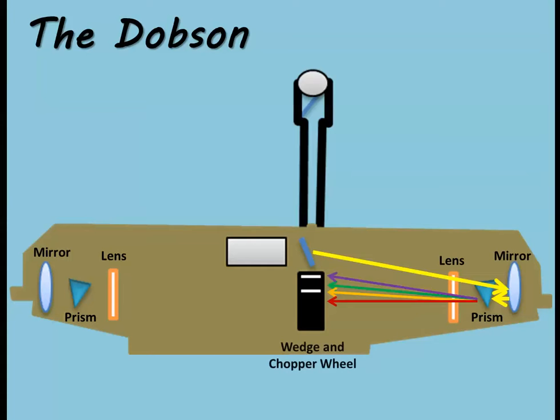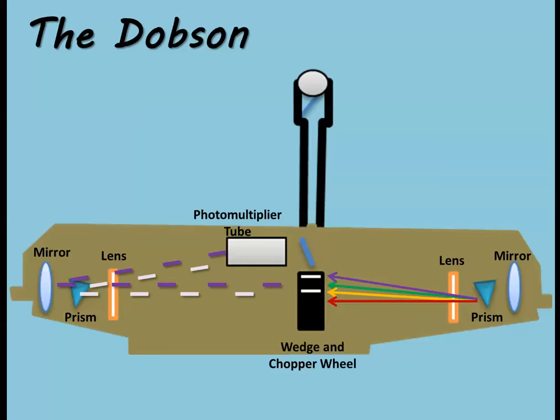This spectrum enters a wedge with slits that allows only certain wavelengths that are affected by ozone molecules through. A chopper wheel inside the Dobson acts to segment the wavelengths, so they can be measured individually.